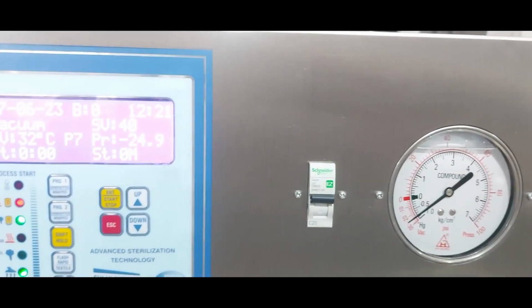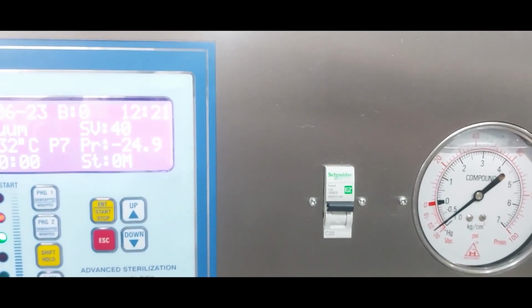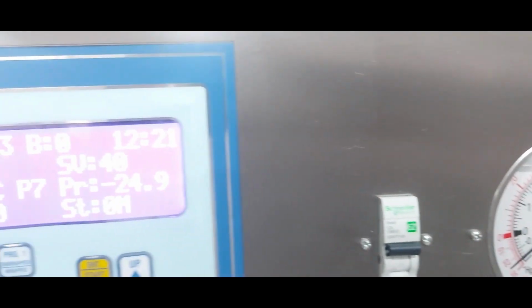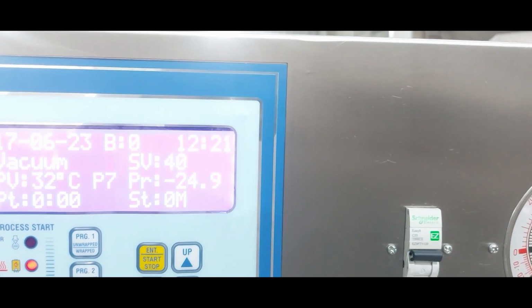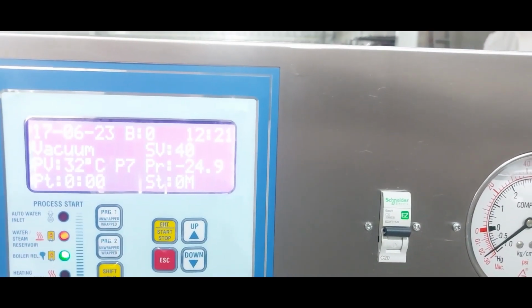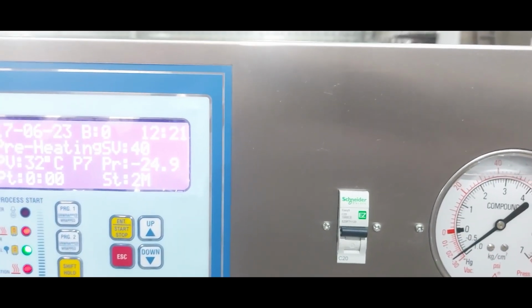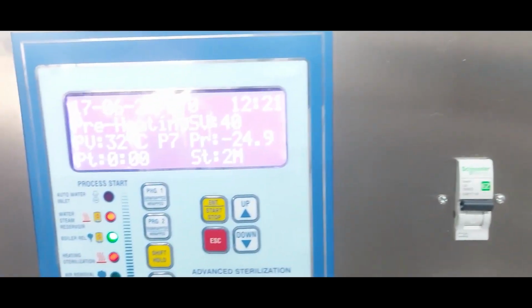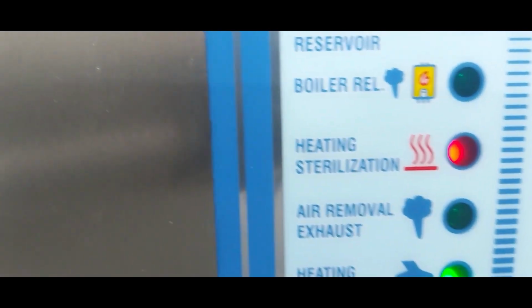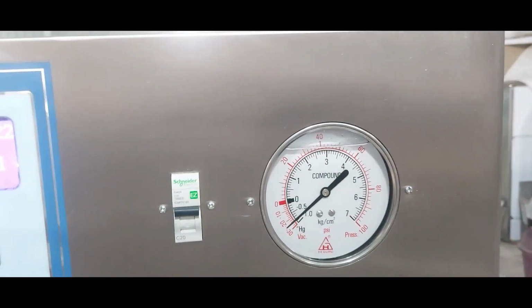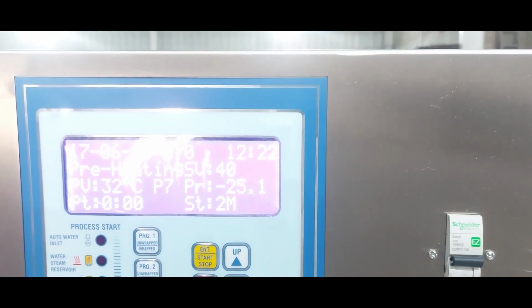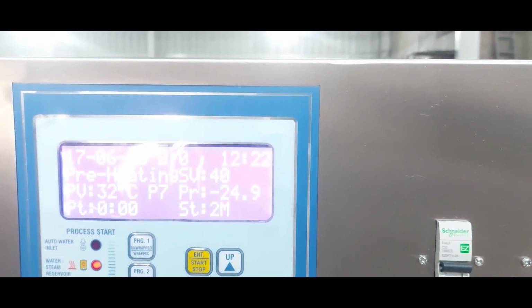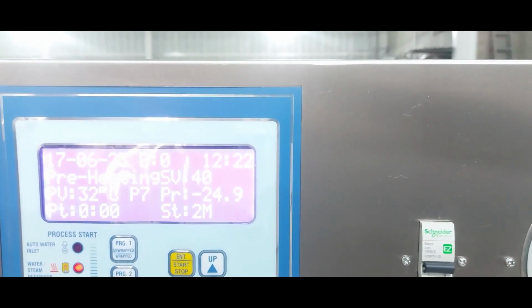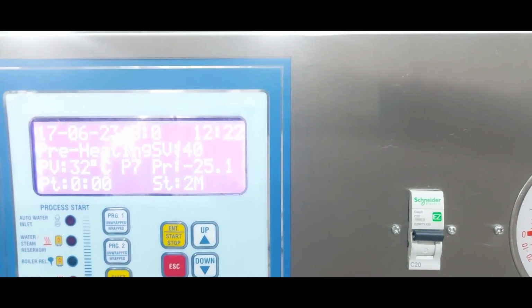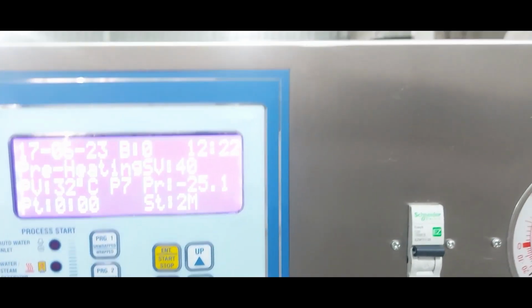Once the vacuum arrives at minus 25, our next cycle of preheating will start. Preheating has been started, and we are maintaining the vacuum at minus 25. Once the temperature reaches 40 degrees, from 32 to 40, it will go into the ETO injection mode.